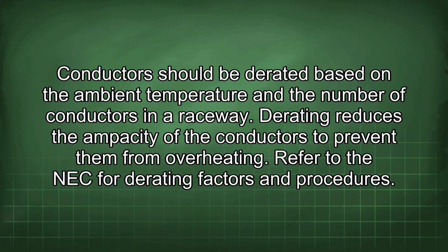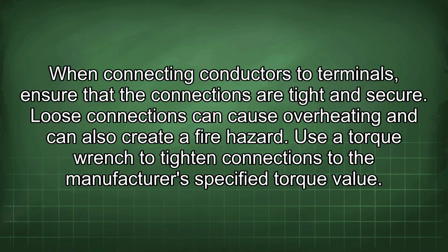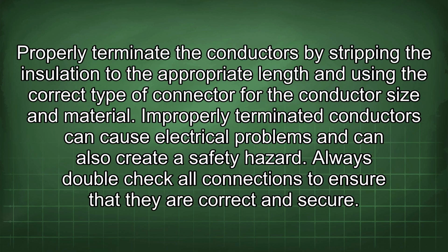Conductors should be derated based on the ambient temperature and the number of conductors in a raceway. Derating reduces the ampacity of the conductors to prevent them from overheating. Refer to the NEC for derating factors and procedures. When connecting conductors to terminals, ensure that the connections are tight and secure. Loose connections can cause overheating and can also create a fire hazard. Use a torque wrench to tighten connections to the manufacturer's specified torque value. Properly terminate the conductors by stripping the insulation to the appropriate length and using the correct type of connector for the conductor size and material.